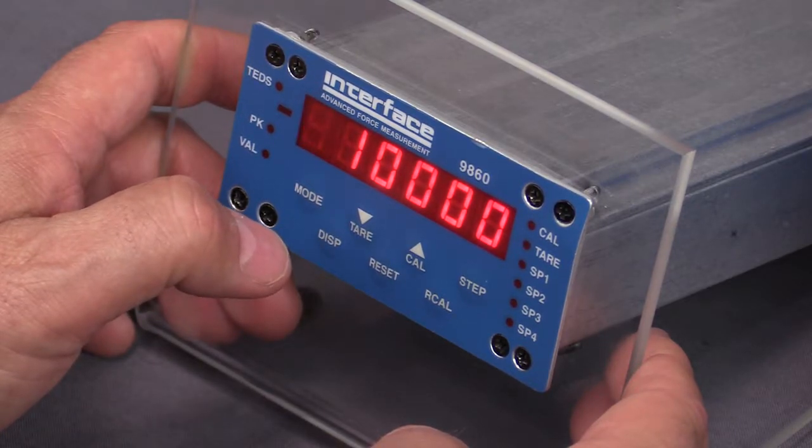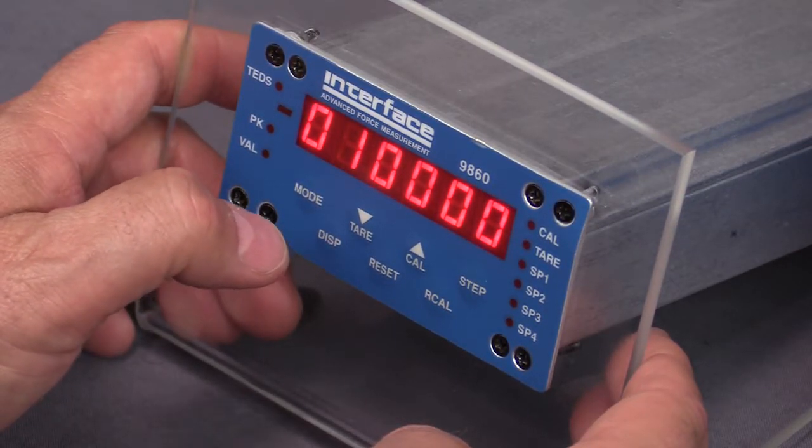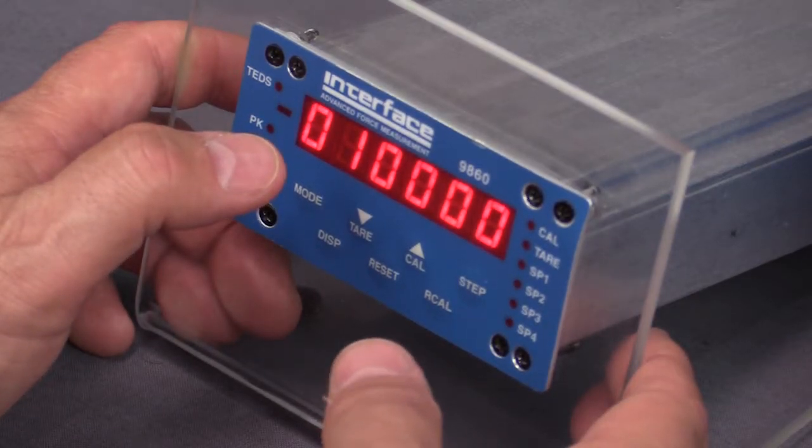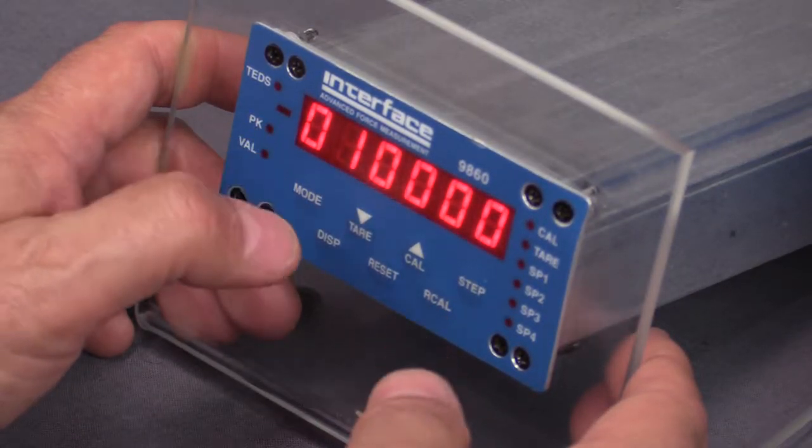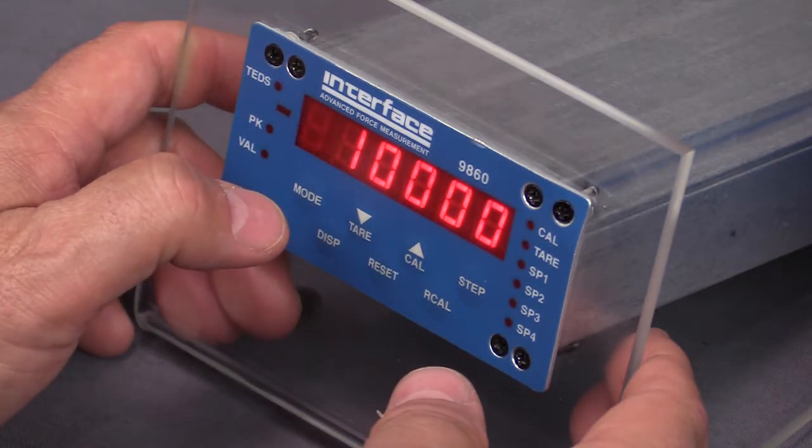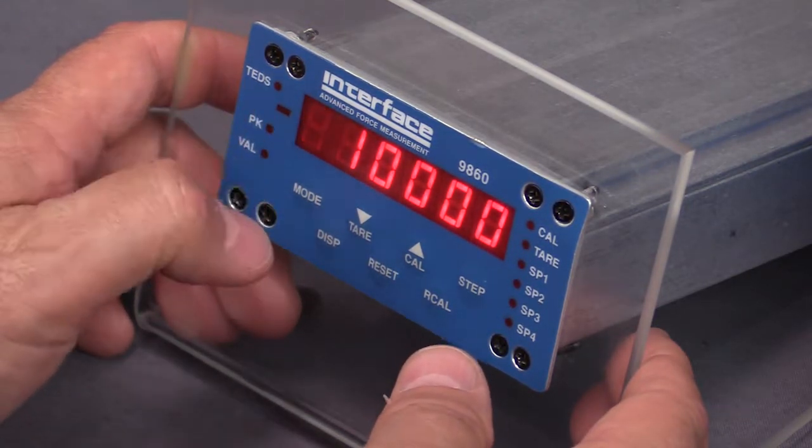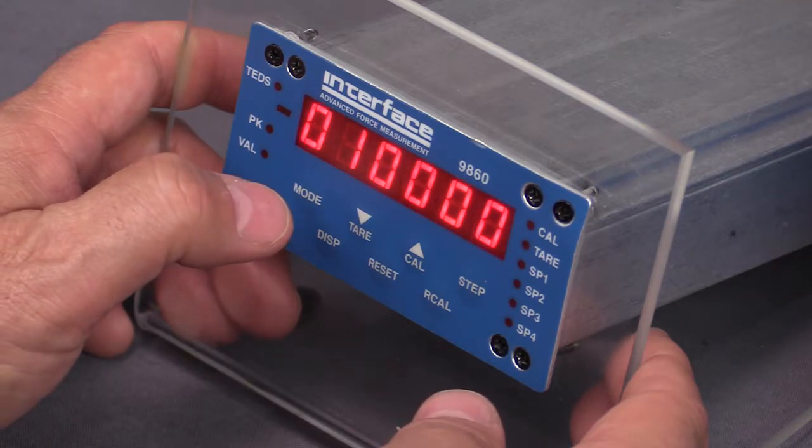FS means full scale. This is where we're going to set the full scale for the analog output. In this case we're going to match it to the full scale of the system, so 10,000 is what we set for the calibration value. For the full scale on this we will set it to 10,000 as well, so that means at 10,000 you'll get a 10 volt output on your analog output.